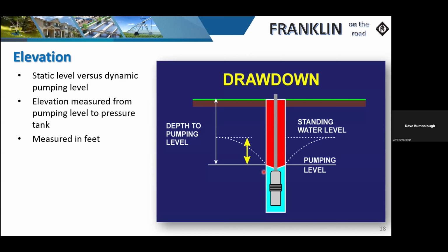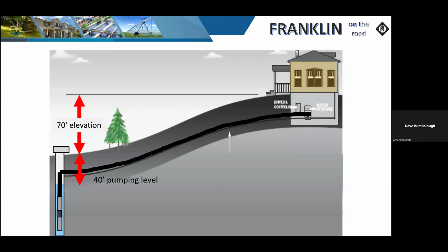Now, I always put two numbers to this. I will draw basically a line that makes it look like a capital T. On one side, I will put where my water starts, which may be an upper level. On the other side of the T, I will typically put where the pump is set, because the water level is never going to draw down past the inlet of the pump. And if it does, then you have major problems at that point. So those are the two numbers I will use, where it starts and then where it's going to end up. And I'll use that calculation when I go to size my pump.